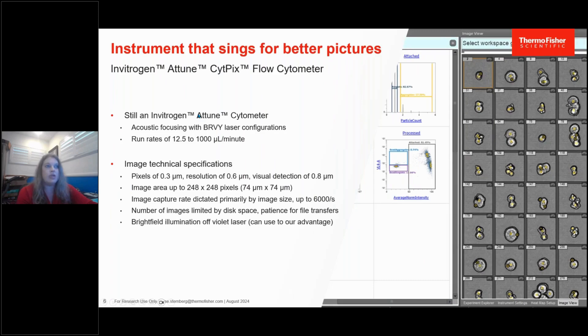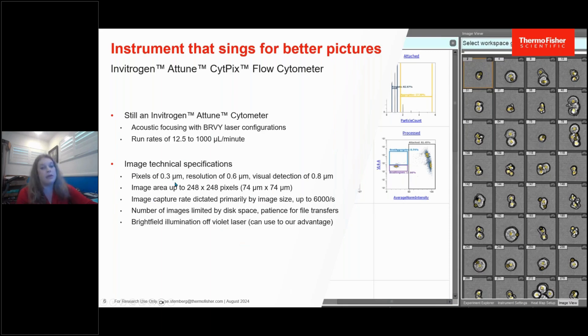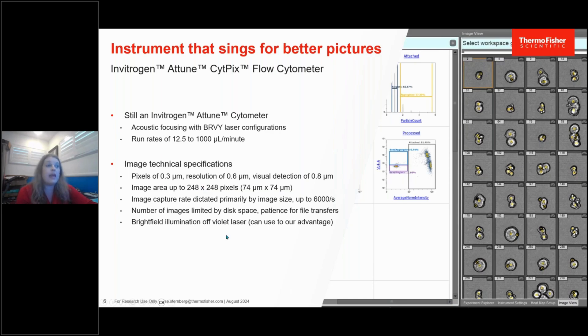The CytPix is added to Attune cytometers with a four-laser configuration: blue, red, violet, and yellow. It has flow rates from 12.5 microliters per minute up to 1 mL per minute. The camera has a pixel size of 0.3 microns, giving a resolution of 0.6 microns and visual detections of 0.8 microns. The image area is variable and can go up to 248 by 248 pixels, or 74 by 74 microns. The image capture rate is 6,000 images per second, limited only by disk space. We also use bright field illumination of the violet laser.